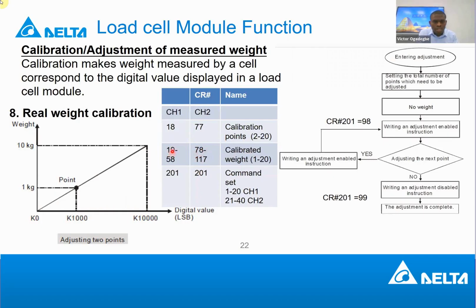this register. This register, 20, runs from 19 to 58 for channel 1, or 78 to 117 for channel 2. So if I write a value in 20, it means it's for position 2 that I've calibrated. The digital value that is there will be what I get from the module. So this is how it goes. First of all, you specify how many points you want to calibrate. It's just 1 register, for 2 points, you write 2. Then once you have specified the number of points, you go to the no-weight point. It's always mandatory to start from 0, when you do not have weight. So you specify the no-weight point, and then you calibrate it.